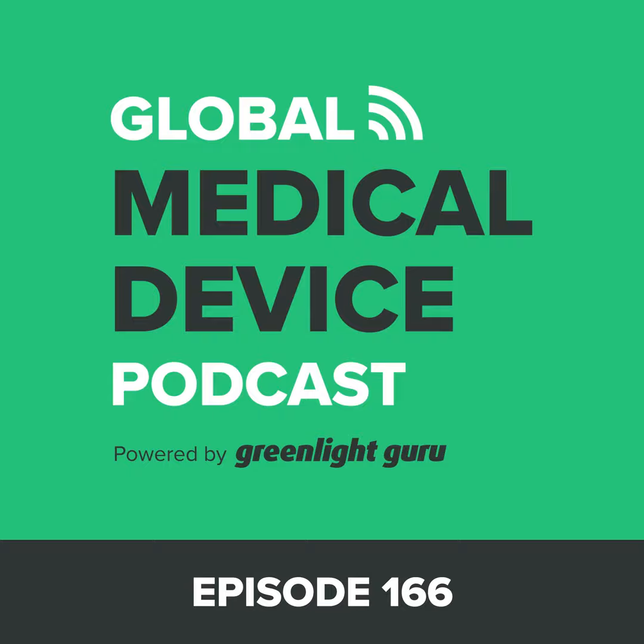identifying biocompatibility testing where it's not necessary, such as through purchasing controls, production process controls, medical device reporting or MDRs, and so on. And as you might guess, John, it's the first one. It's the purchasing controls that concerns me the most here. In other words, they're advocating using purchasing controls as a form of risk mitigation. Now, in some cases, that might be appropriate, but here's the concern I have.